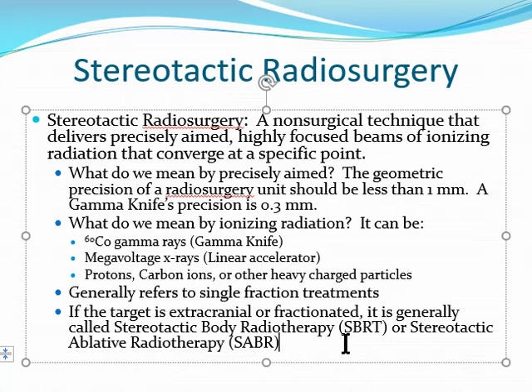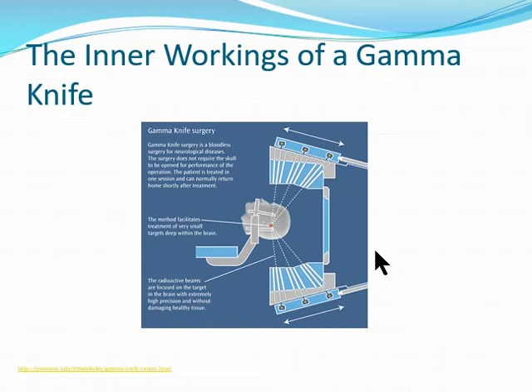As I alluded to earlier, on the inside of the gamma knife, you basically have a point, and your mission is to get the patient's tumor to go into the point of the machine where the high dose is. You have 199 sources, somewhere around that. It's a little less than 200, of cobalt-60. It's giving off radiation in all directions, but it's completely shielded. So there's only one little collimator hole where the radiation beam can get out. We have different sizes of collimators, but they're all pointed to the same point. So everything's relatively weak around it, but you have this high dose point in the center. So it's a really elegant way of delivering focused radiation in the brain.